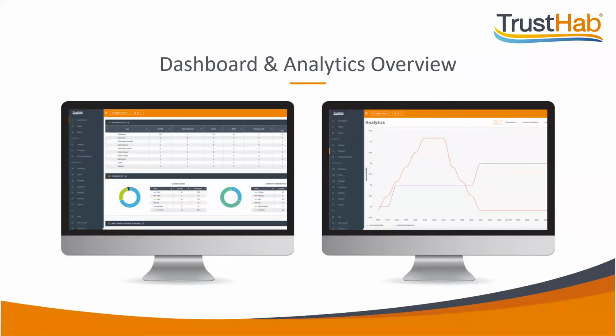The best examples of potential cost savings have been locating and remedying the units that are running excessively. The initial 24 hours after an installation shows you really which units struggle to reach their set points, if they even reach them at all. Those units have likely been running like that for months, if not longer. And you'll be able to easily see your property and building runtime averages, so you can locate the units which are outliers and likely need more maintenance. Runtime data also allows us to project savings if you set hard cooling minimum and heating maximum set points. And this can correlate directly to a percentage of runtime savings.